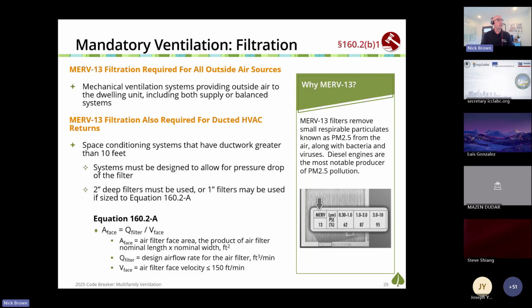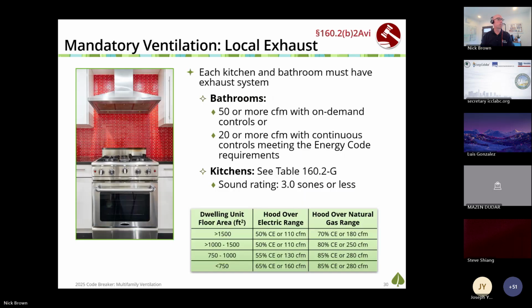There is an exception on the ducted HVAC systems that you can use a 1-inch filter, but you have to meet this equation. Easier to just use that 2-inch deep filter. We've also got a mandatory requirement for local exhaust systems. Every kitchen and bathroom have to have exhaust systems. These requirements are unaffected by the whole dwelling unit IAQ fan prohibition on exhaust. Don't get that confused. And bathrooms need to have a 50 or more CFM airflow with on-demand controls, or also acceptable 20 or more CFM with continuous operation.